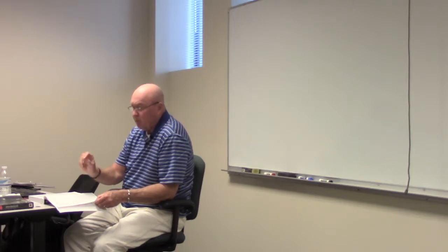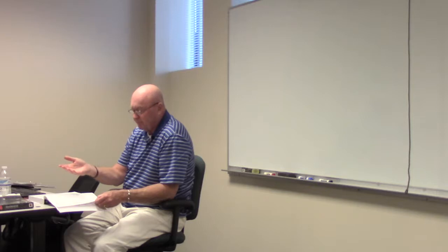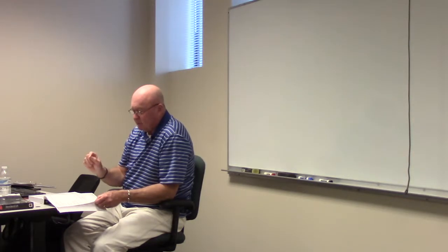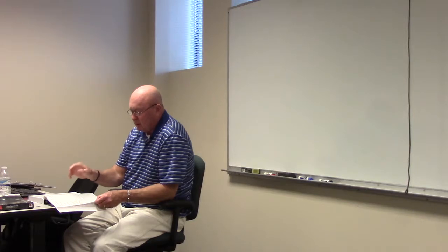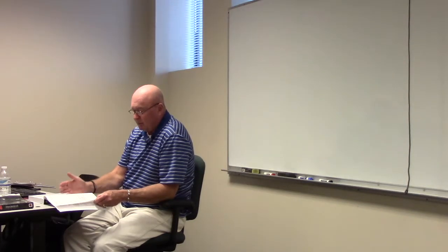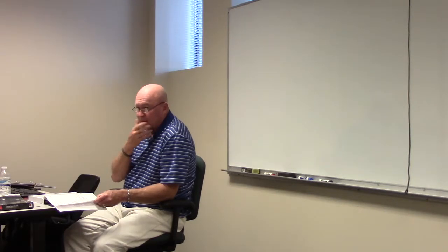And then we got 1.25, because don't y'all agree, the restaurant lighting is gonna be continuous? And so we see here that it's 1.25 times 2 VA, times 1,000 square foot, divided by 120 volts is what? It says it's 20.8 amps, okay?